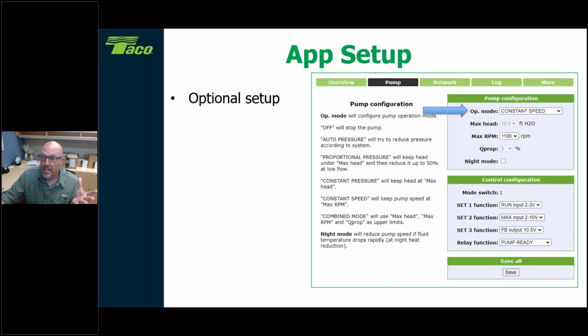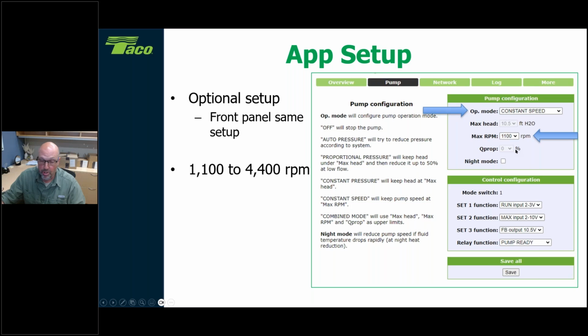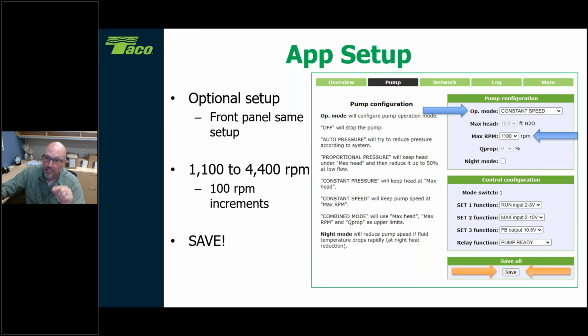You can see here that it also tries to make it so you can't choose incorrect settings for one application versus the other. Right now you choose the operation mode of constant speed, and right below that, max head is grayed out, meaning you can't change the head of the circulator, because that's not the mode you're in. You have the option to change your RPMs, so that one is lit up. Now, Q proportional means I can change that proportional setting. Two weeks ago, we talked about the proportional being set on a 50% incline or decline. Here you get to change that proportion, so if you need it steeper or flatter, you can do that here. And here's your checkbox for night mode. Just choose it, remember to choose those RPMs in 100 RPM increments, and make sure you click save. It's the same as on the faceplate where you hit that set button again. You have to hit that save button on the screens themselves, otherwise it just goes back to where it was before.